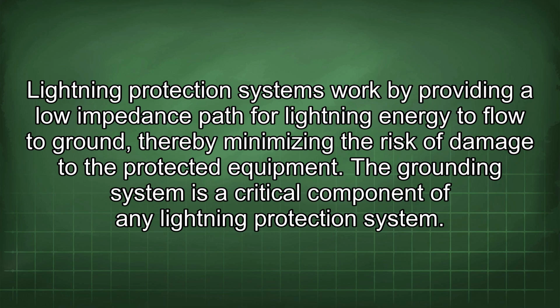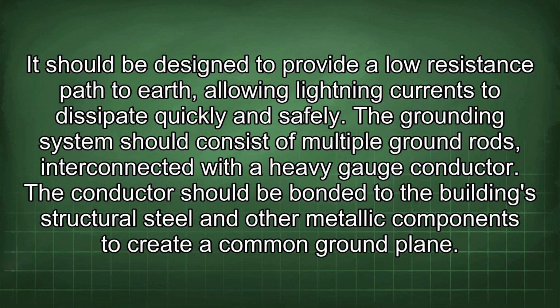Lightning protection systems work by providing a low impedance path for lightning energy to flow to ground, thereby minimizing the risk of damage to the protected equipment. The grounding system is a critical component of any lightning protection system. It should be designed to provide a low resistance path to earth, allowing lightning currents to dissipate quickly and safely. The grounding system should consist of multiple ground rods interconnected with a heavy gauge conductor. The conductor should be bonded to the building's structural steel and other metallic components to create a common ground plane.